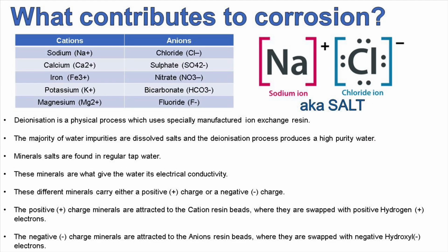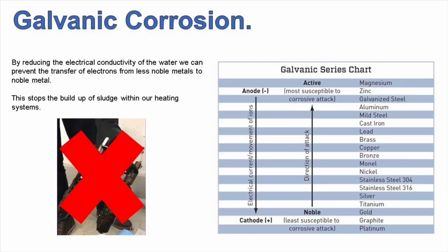So you're probably wondering what all these tests mean and why we're doing it. There's a connection between the TDS and the conductivity. Essentially water is full of minerals, and minerals have different charges. So there are actually small amounts of electricity in water. You have what's called your cations and your anions. These charges are what give the water its electrical conductivity. So if we reduce our TDS, we reduce the amount of conductivity. So why are we reducing the conductivity? We're doing that to stop galvanic corrosion.